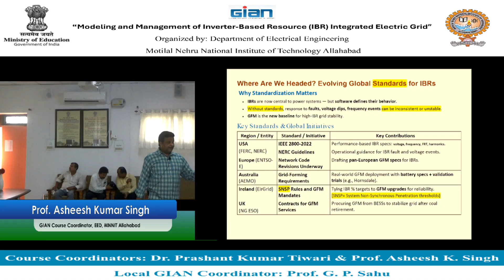Then comes Ireland, with the EirGrid SNSP rules and GFM mandates. I already told you what SNSP is, that is system non-synchronous penetration threshold. They are tying IBR percentage targets to GFM upgrades, to reliably increase the percentage of IBR. Why not get to 100%? I already gave you the example of the Irish grid - they are trying for 100% by 2035.